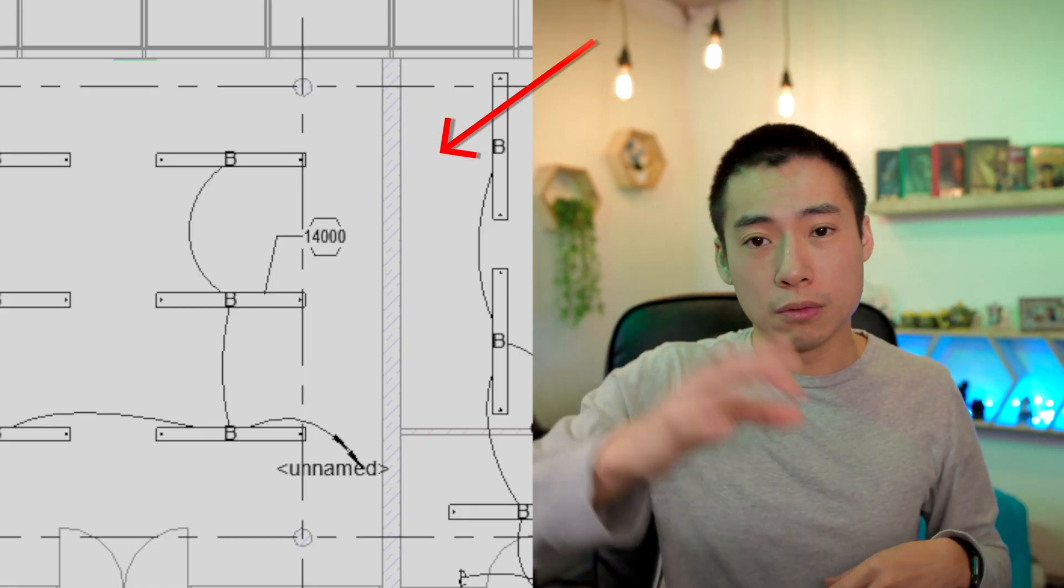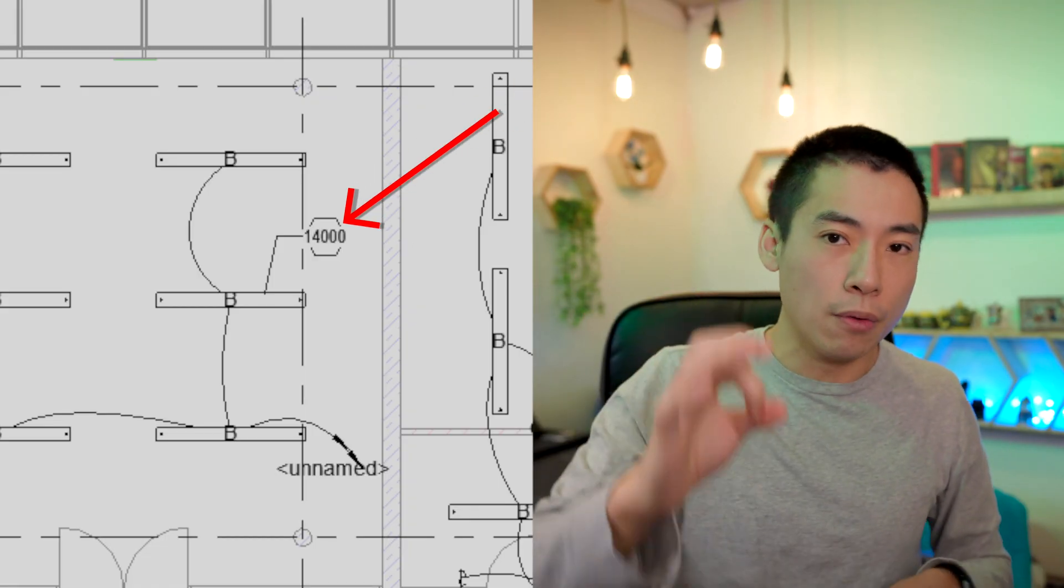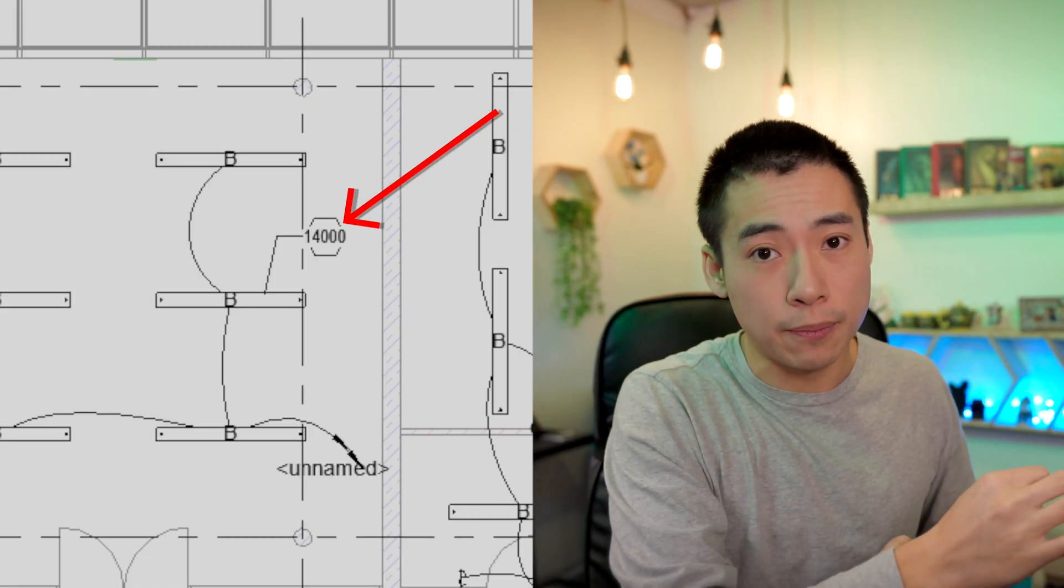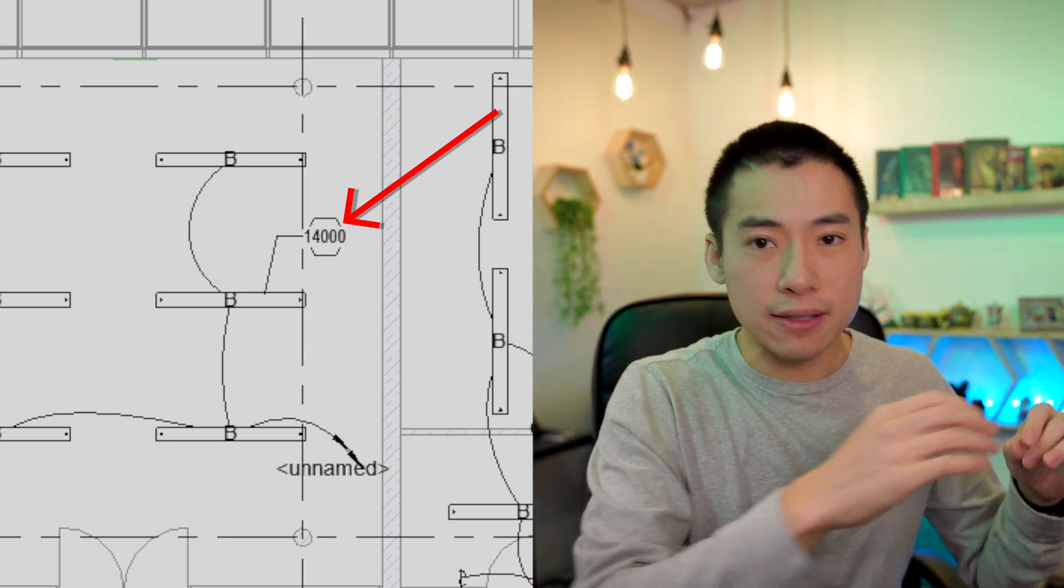So the other way you can do it is to use Revit Keynotes. Revit Keynote places a symbol on the floor plan and it links it to the note that's on the side of the drawing. Or you can actually put the notes on a dedicated note sheet if that's your thing. It's only a couple steps. You have to make a file, link it in, make a schedule, a legend schedule, and then put the Keynotes on the floor plan. So let me show you how we do that.